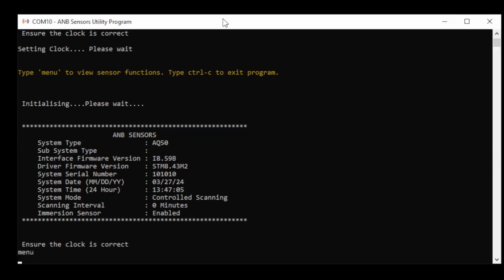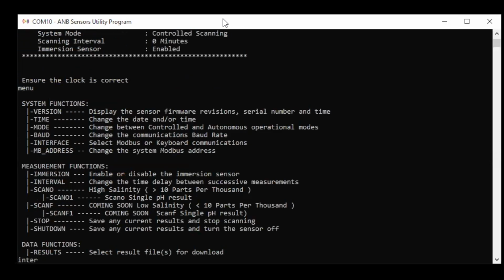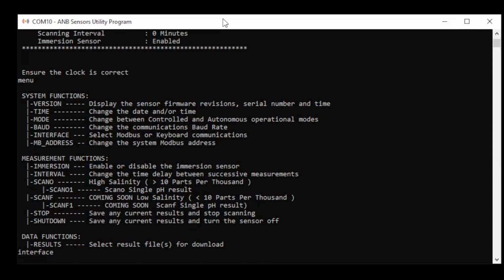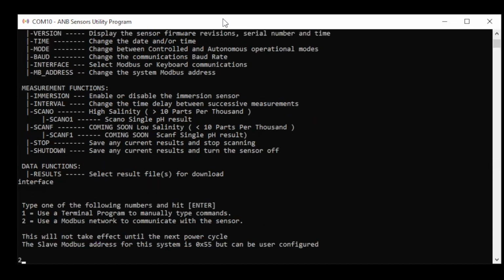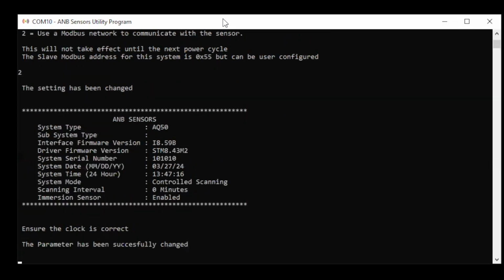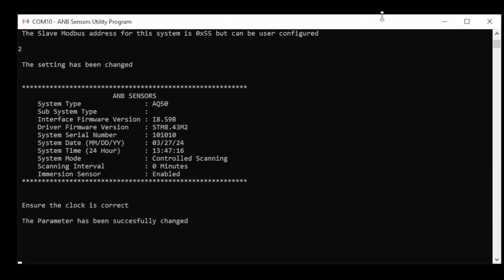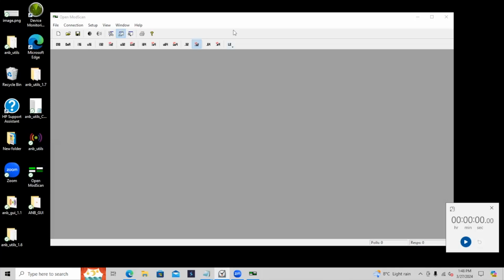We then type menu, we select interface from the menu, we select option 2. The sensor will now be in Modbus mode. To verify, we can turn the sensor on while still in utils. And you can see there's no response given. We can now close utils and open ModScan.